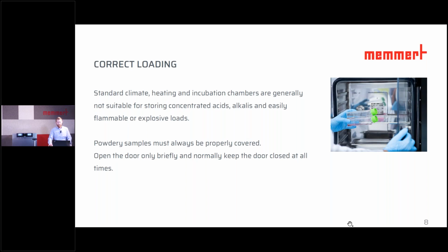Door opening should always be as short as possible. That's why incubators, but also climate chambers, which can regulate not only temperature but also humidity, are equipped with an inner glass door. The recovery time after the door is opened for temperature is usually faster compared to the time it takes to reach humidity levels and, if necessary, gas concentrations again. Therefore, especially with this type of device, the doors should only be opened briefly to keep the impact on the samples as low as possible.